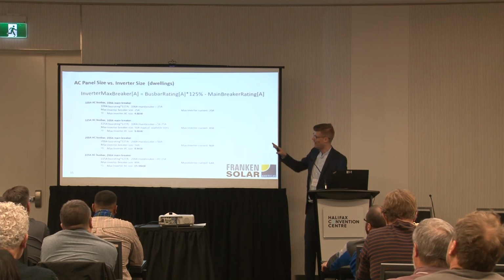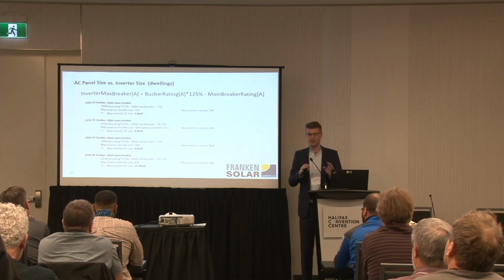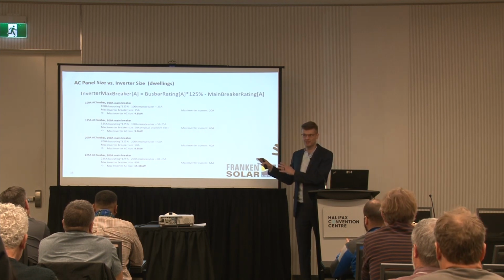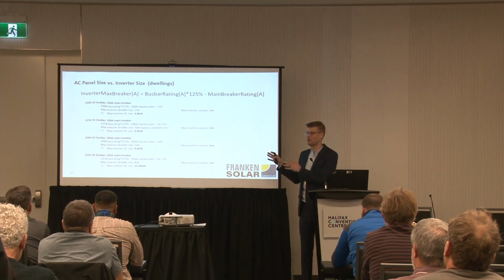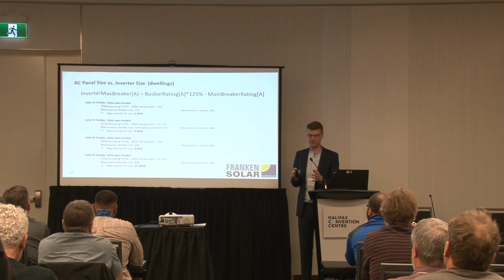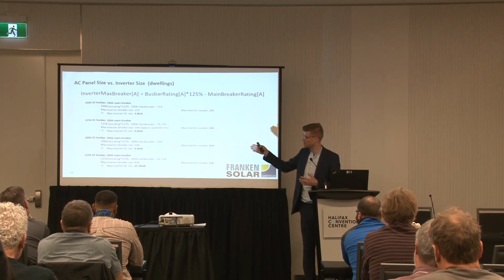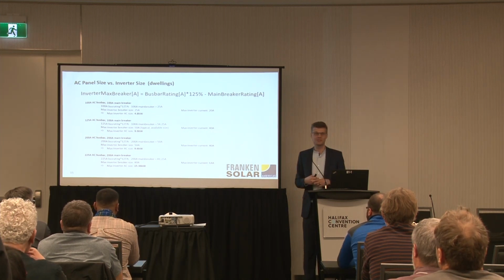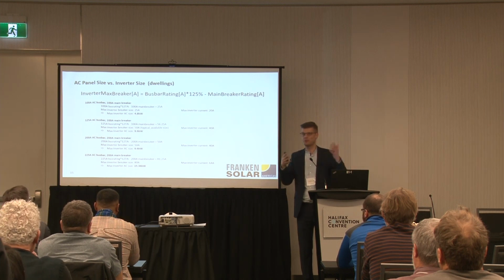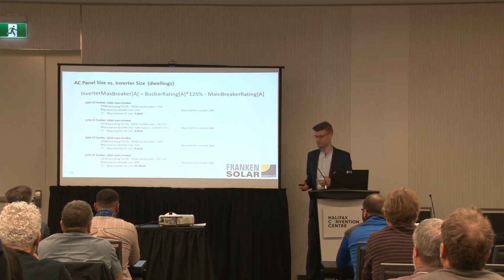So understanding that it's not only a financial perspective of what equipment you buy, but if you look closer at what the customer already has, you can save the customer $2,000 or $3,000 just by looking one more time at the electrical panel and selecting the inverter that fits exactly in that existing infrastructure size. For example, you can put a 7.7 kilowatt inverter on a 125 or 200 amp busbar, and you size the system to 10 kilowatts. So there you have a 1.3 to 1 DC to AC ratio, or you even push it harder and put 1.5 on.